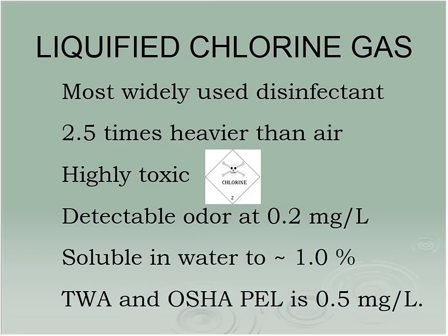It'll kill you if you let it. It's 2.5 times heavier than air, so any leaks tend to pool distinctly at floor level. It's highly toxic. You can smell it at very low concentrations. Just walk through our laundry area when my wife's doing white shirts. It's quite soluble in water. The OSHA PEL, permissible exposure limit, is half a part per million in air. Half a part per million. And if you read the regulation, you'll also find out that OSHA states that nobody should be exposed to more than one part per million. There's not a whole lot of buffer there. But you shouldn't be smelling it.